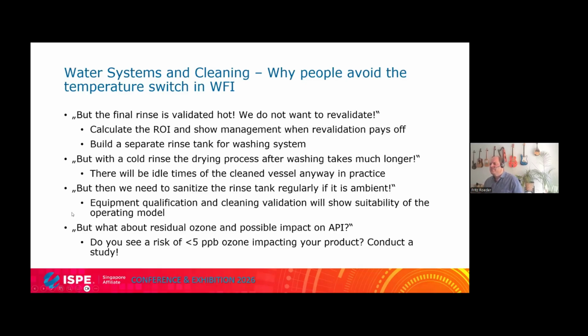Last one: but what about residual ozone and its possible impact on the API? This is also a tough one, a very frequent question. The topic is, if we have an ozonated cold loop, we measure the residual ozone after the UV. The best measurement technology and calibration methods on the market go down to 5 ppb in practice. In the lab, in theory, under best conditions, you can get better accuracy, but not in routine. We've checked it out.